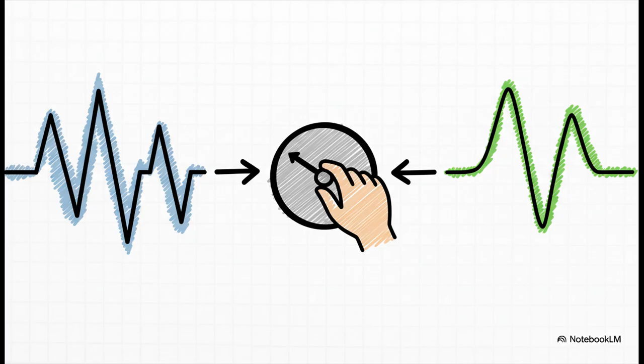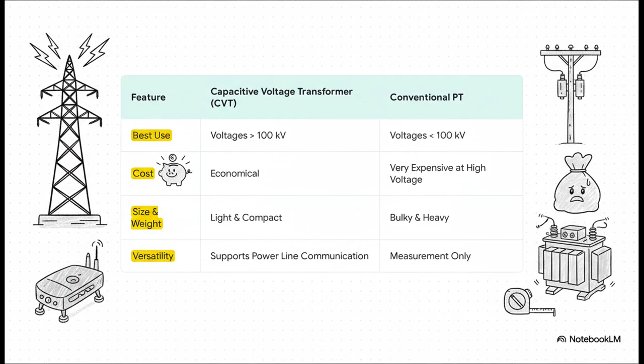Now that we've got a handle on how a CVT works, let's put it head-to-head with the old technology, the conventional potential transformer, or PT. The differences are pretty dramatic. While a traditional PT is fine for lower voltages, the CVT is the undisputed champion in high voltage situations. It's way more economical, significantly lighter and more compact, and offers a level of versatility the old guard just can't touch. The key takeaway, the magic number to remember, is anything above 100 kilovolts. That's the point where the cost savings and practical benefits of the CVT make it the absolute no-brainer choice for high-voltage power systems.